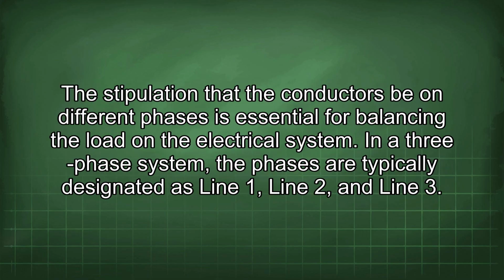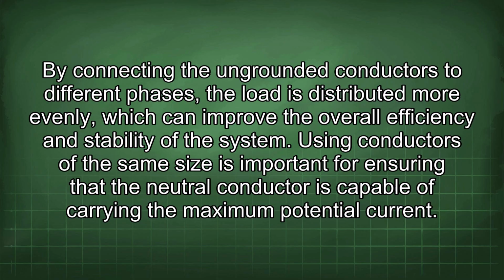The stipulation that the conductors be on different phases is essential for balancing the load in the electrical system. In a three-phase system, the phases are typically designated as line 1, line 2, and line 3. By connecting the ungrounded conductors to different phases, the load is distributed more evenly, which can improve the overall efficiency and stability of the system.